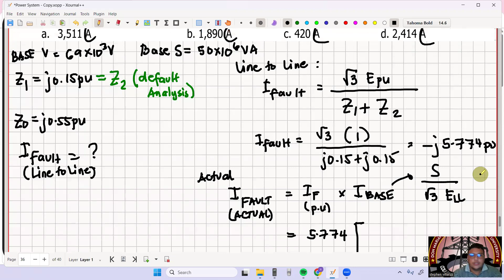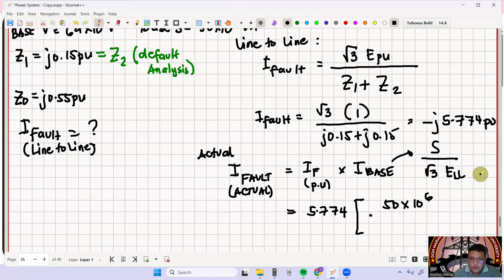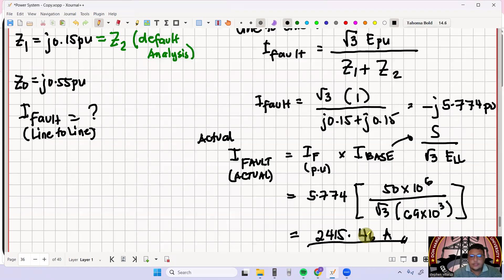That is S over square root of 3 multiplied by your E line-to-line or baseline-to-line voltage. So this is now 50 times 10 raised to 6 all over square root of 3 multiplied by 69 kV. Multiply lang natin to: 50 mega all over square root of 3 multiplied by 69 kilo, so therefore this is equal to 2,415.46 amperes.